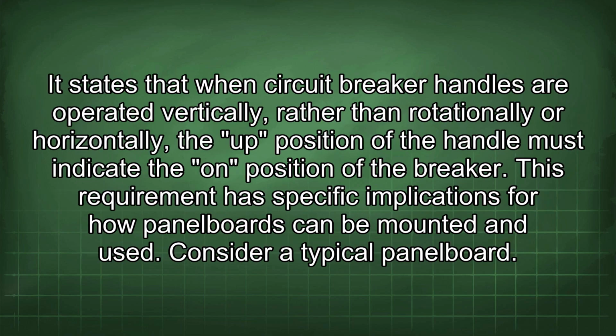It states that when circuit breaker handles are operated vertically, rather than rotationally or horizontally, the up position of the handle must indicate the on position of the breaker. This requirement has specific implications for how panel boards can be mounted and used.